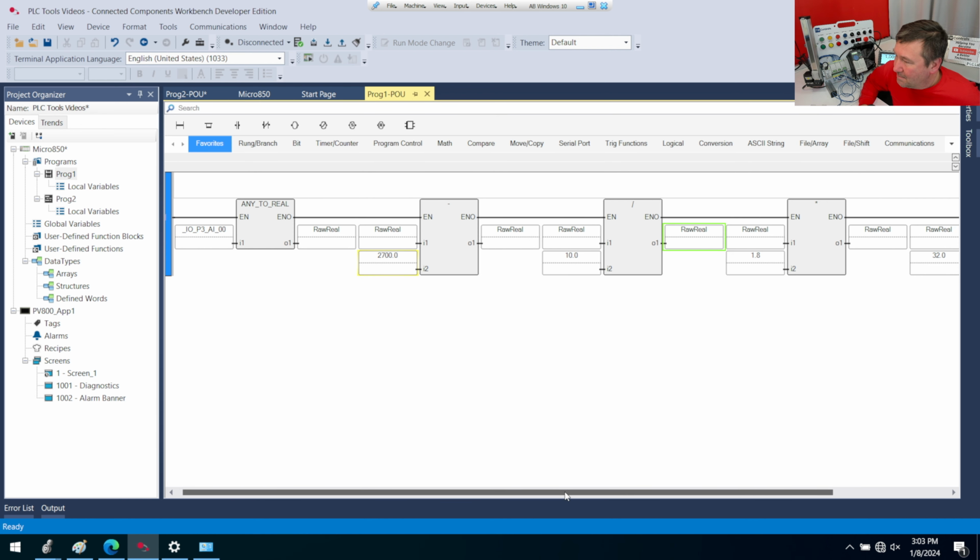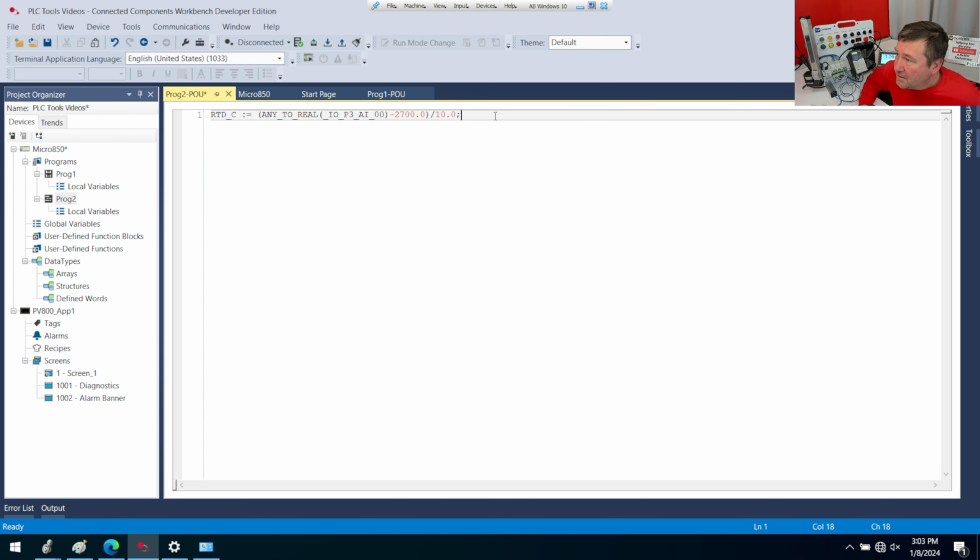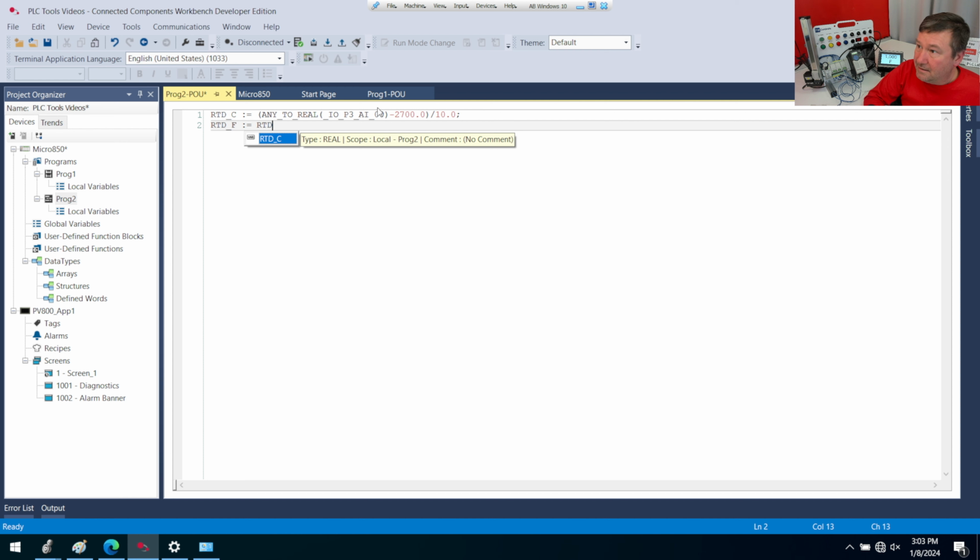All right, now we want to take this and go ahead and take it to Fahrenheit also. And that's what this last part here was doing, because really we got it to here. And then we multiply it by 1.8 and we added 32. And that's the conversion from Celsius to Fahrenheit. So we're going to just hit the enter key on this. And we'll do this one the way you typically would type it in structured text. And I would put RTD_F and then colon equals. And we don't need any of that above because we already have it here as RTD_C.